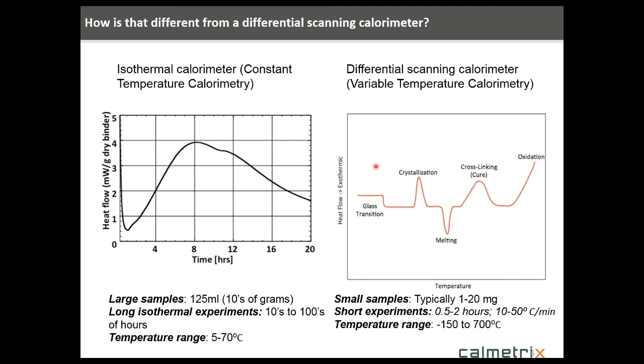Baseline is very important in this instrument, as it is with many analytical instruments. The instrument is designed to provide very long-term baseline stability, which is very important to us for these applications because it provides the sensitivity that we need to very small changes in heat flow over very long time scales. Baseline stability is just as important in these applications as your raw signal noise in terms of being able to pick up small transitions in samples that happen over these very long time scales, and that's what the instrument's designed to do.